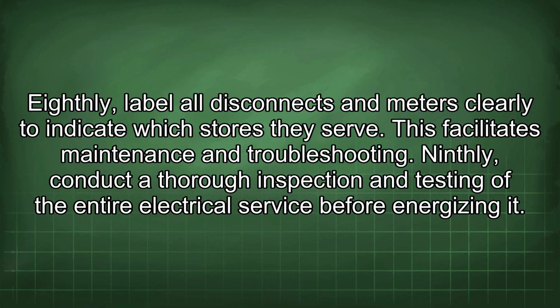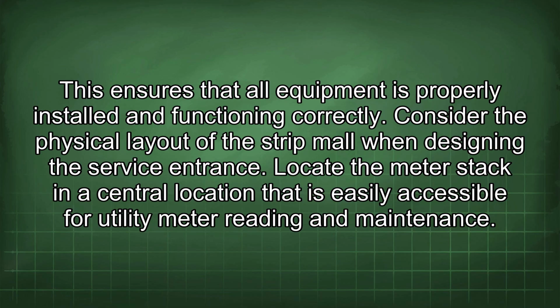Ninthly, conduct a thorough inspection and testing of the entire electrical service before energizing it. This ensures that all equipment is properly installed and functioning correctly. Consider the physical layout of the strip mall when designing the service entrance. Locate the meter stack in a central location that is easily accessible for utility meter reading and maintenance.